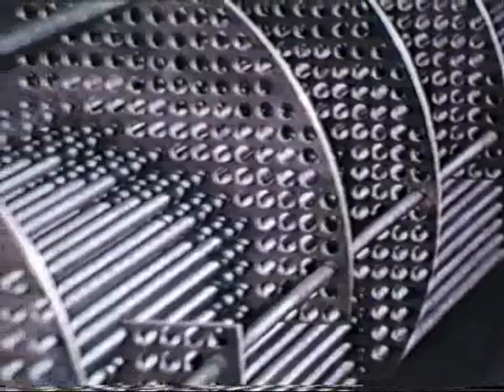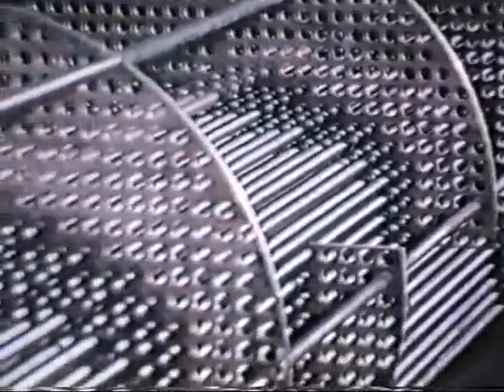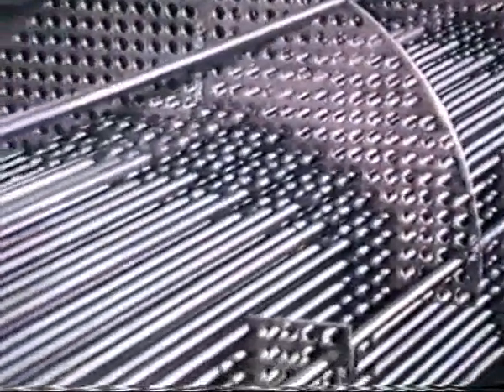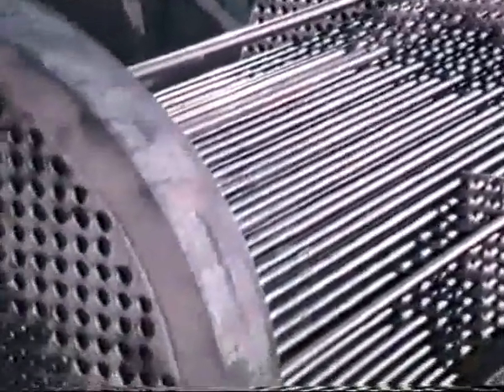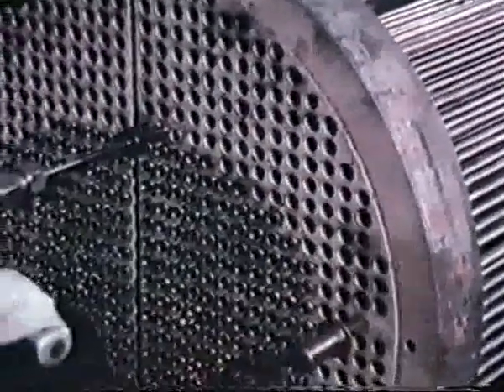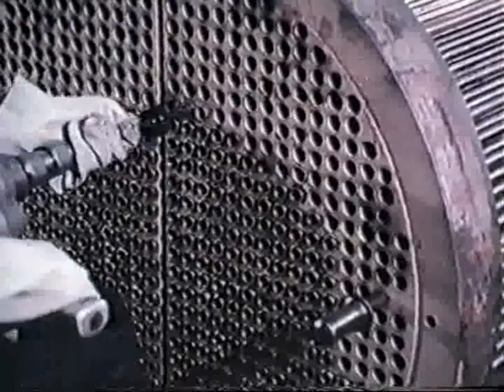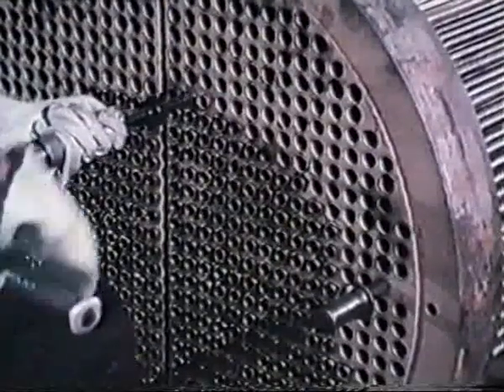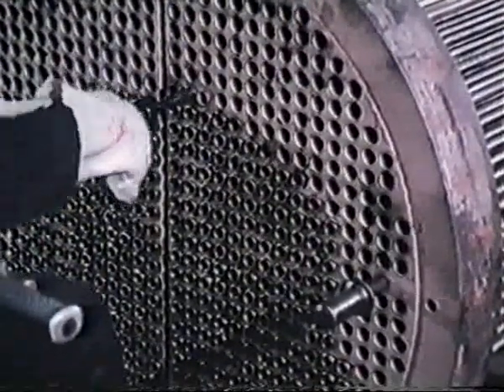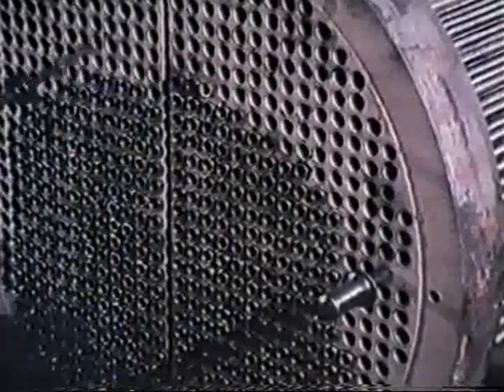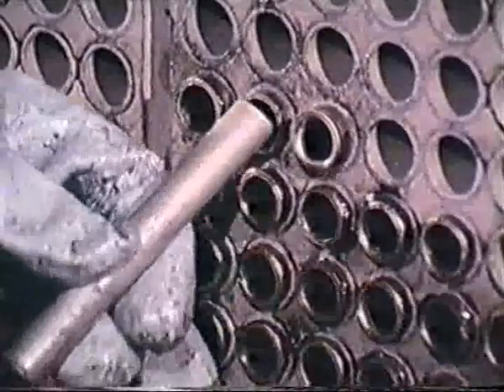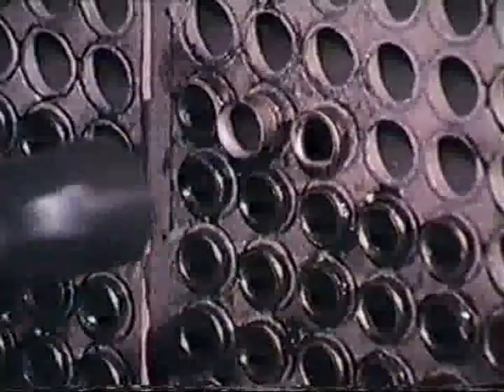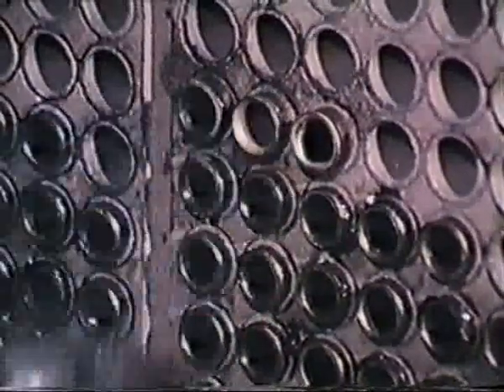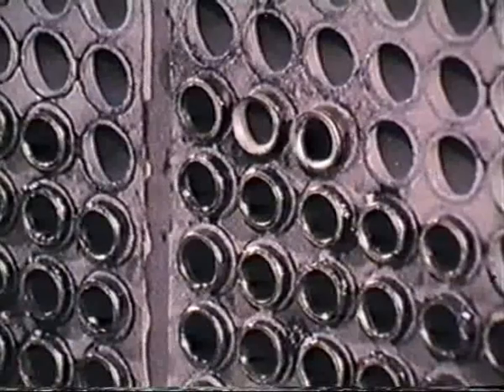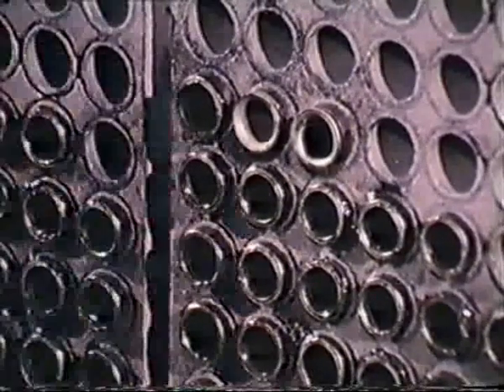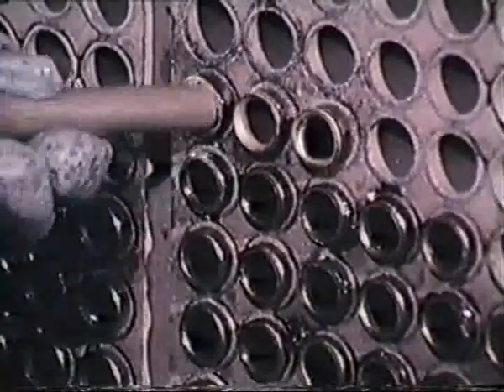In cooling tubes, erosion corrosion does not usually occur along the whole length of the tube, but at the inlet where turbulence occurs. So, for economy, protective inserts are used, which, when eroded, may be replaced at shutdown. The period between maintenance is doubled, and with new inserts, the life of tubes is prolonged for many years.